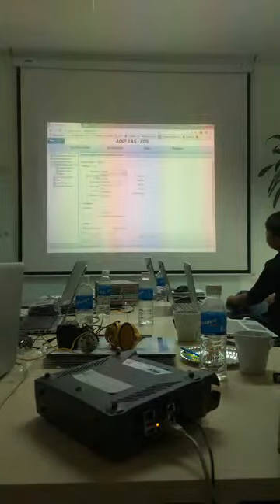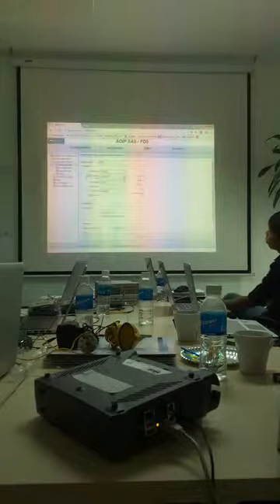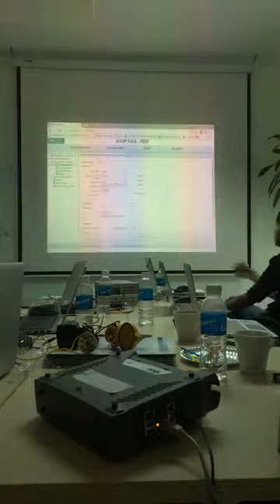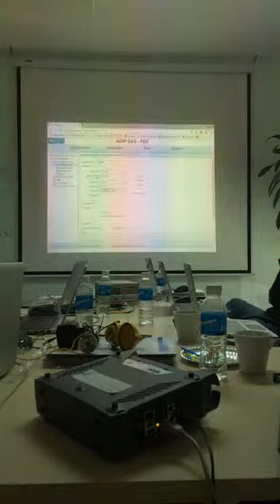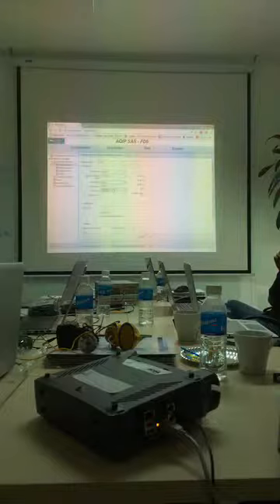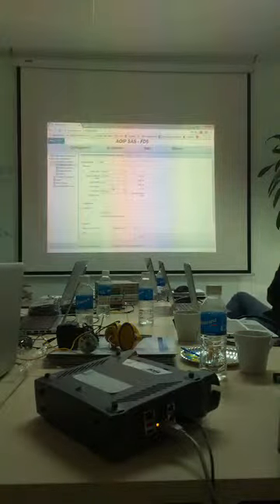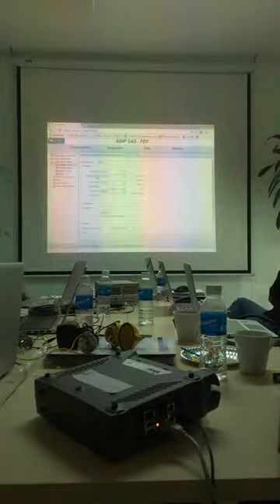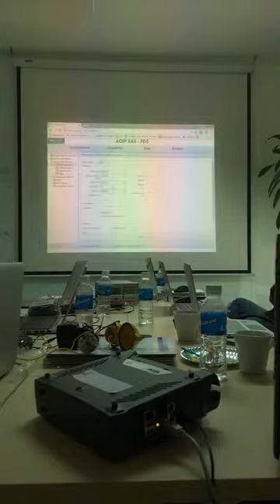Okay? We can put current. So same, we select the right range. Is the scale linear or quadratic? Because both exist on the market. The accuracy, okay? Connection you cannot change because if it's 4-20 milliamps, connection is always the same. It's not like PT100, sometimes 2, sometimes 3, sometimes 4 wires. Connection is there to identify the connection. Physical unit will remain like this.